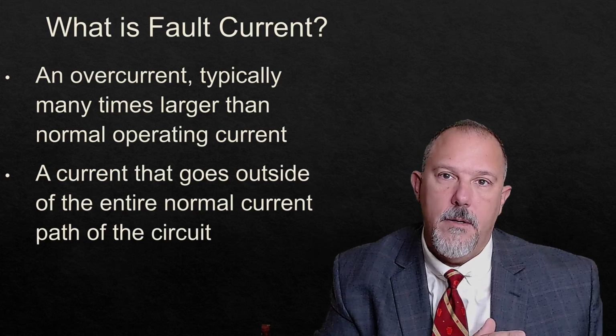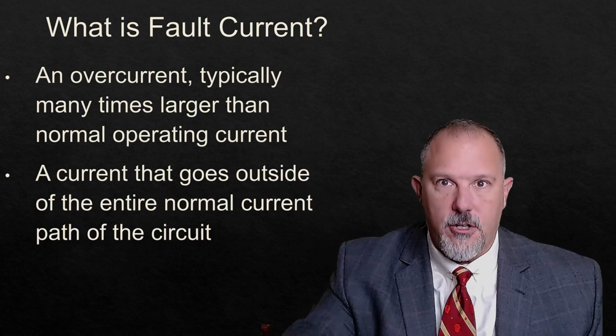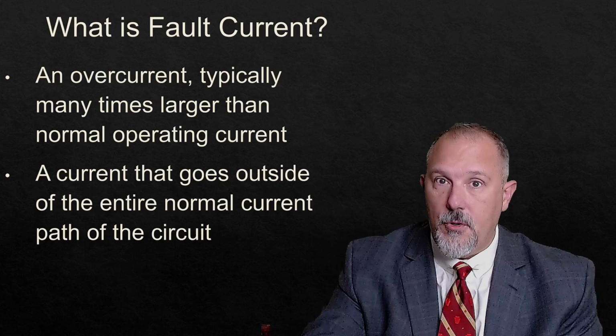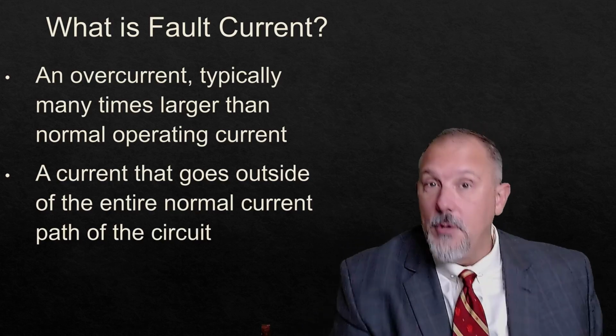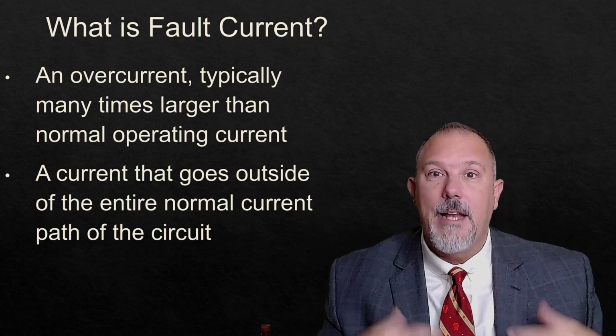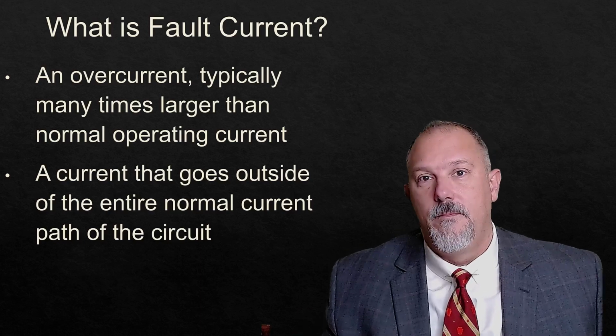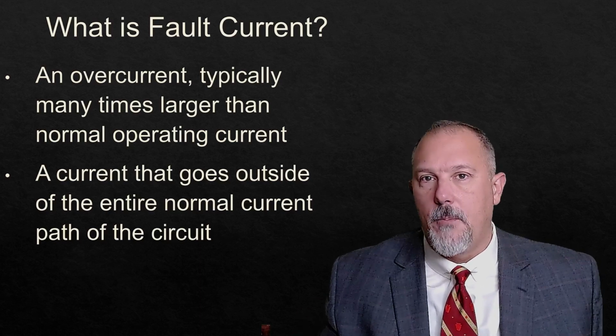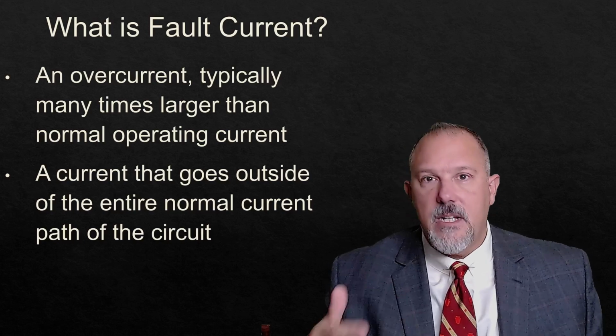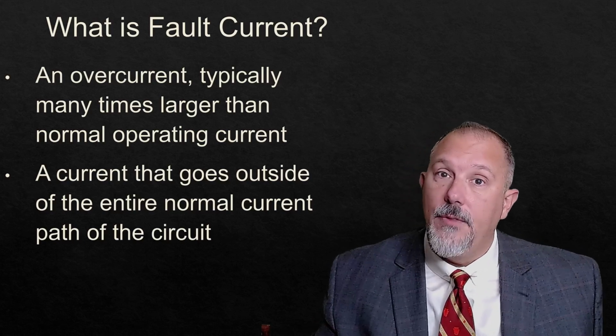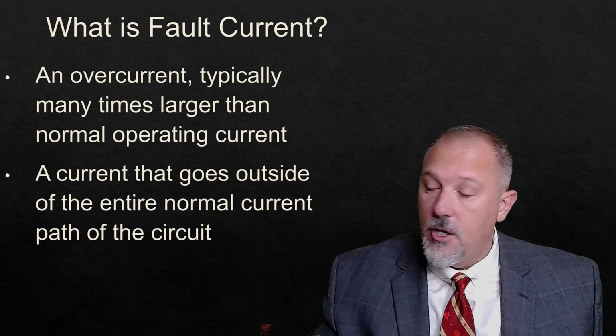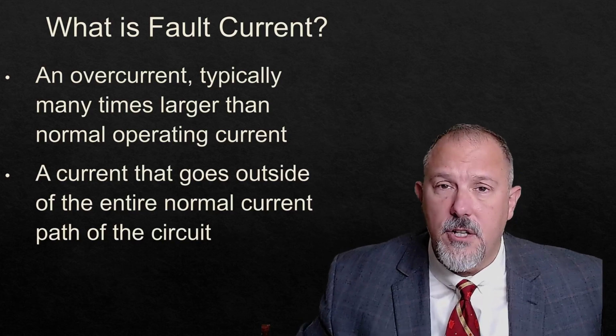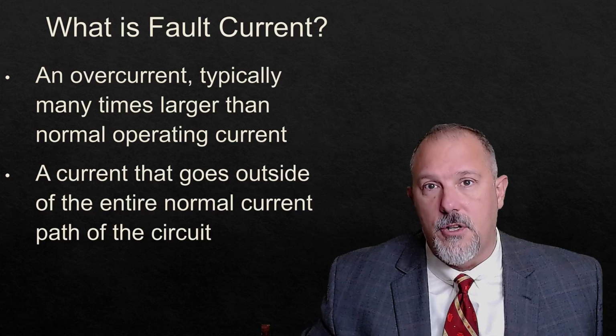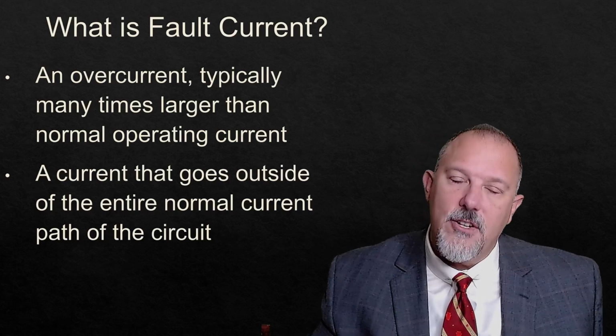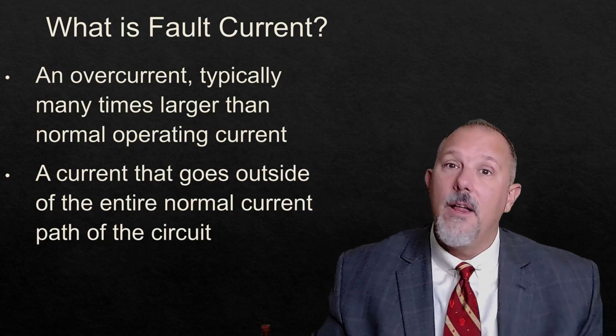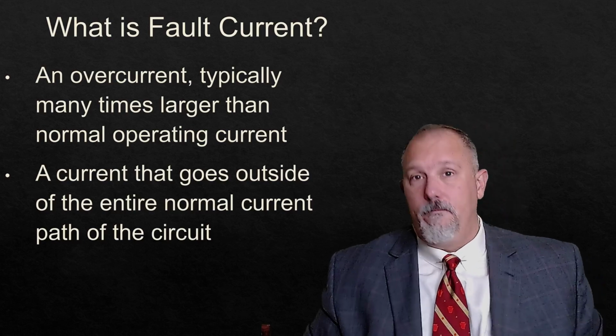saw when it opened. Now, if you have a circuit breaker that has, say, an electronic trip unit in it, maybe it is communicating with a computer, you could actually capture the waveform, depending upon the technology in the circuit breaker, which will probably be dictated by the size and the type of circuit breaker you're dealing with. It could still be a molded case circuit breaker, but your insulated case and your power circuit breakers will typically have electronic trip units that have a lot more functionality than probably what you know.